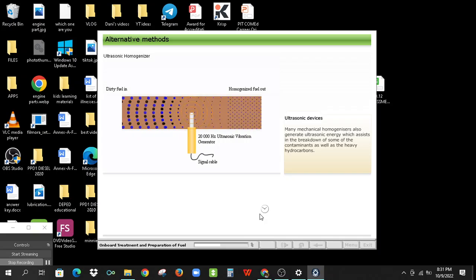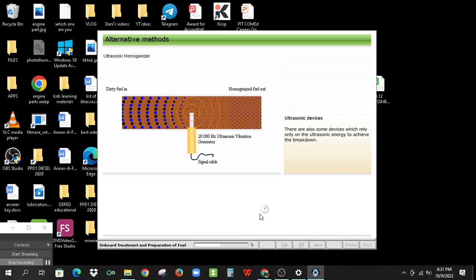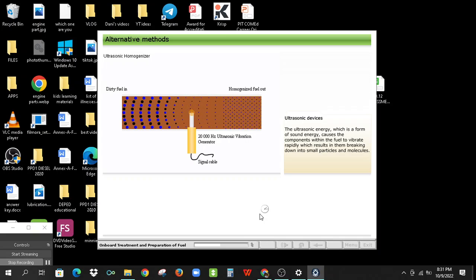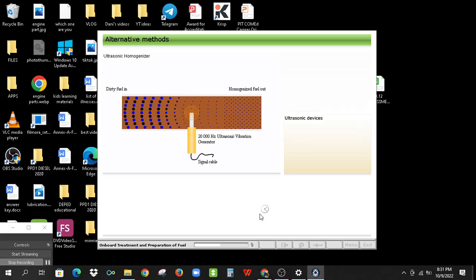Many mechanical homogenizers also generate ultrasonic energy, which assists in the breakdown of some of the contaminants, as well as the heavy hydrocarbons. There are also some devices which rely only on the ultrasonic energy to achieve the breakdown. The ultrasonic energy, which is a form of sound energy, causes the components within the fuel to vibrate rapidly, which results in them breaking down into smaller particles and molecules. You may have come across similar lower energy devices which are used for cleaning components by shaking the dirt from them. Cleaning of heat exchanger plates can be achieved this way.